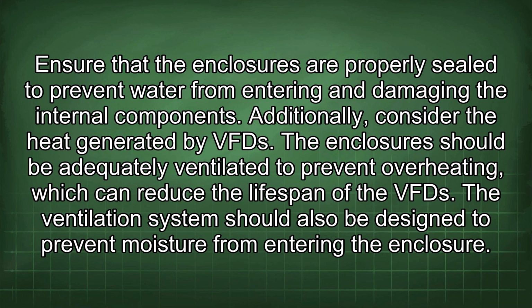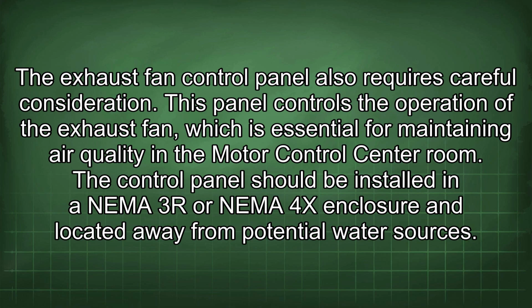Additionally, consider the heat generated by the VFD. The enclosures should be adequately ventilated to prevent overheating, which can reduce the lifespan of the VFD. The ventilation system should also be designed to prevent moisture from entering the enclosure. The exhaust fan control panel also requires careful consideration.